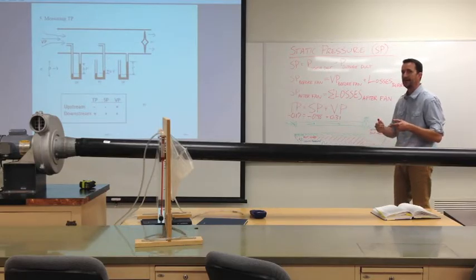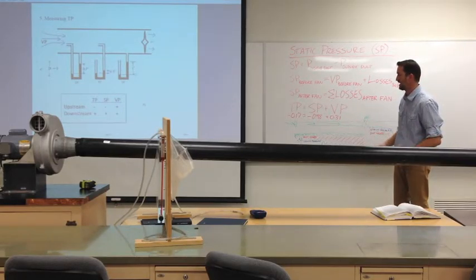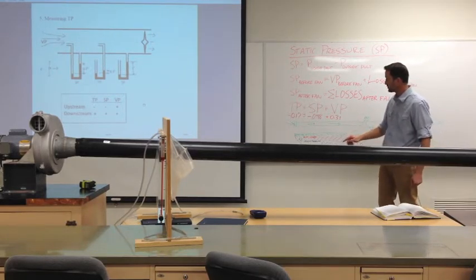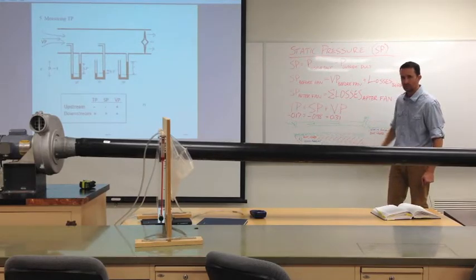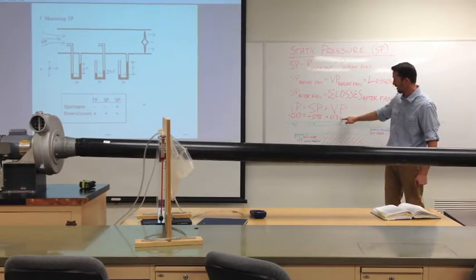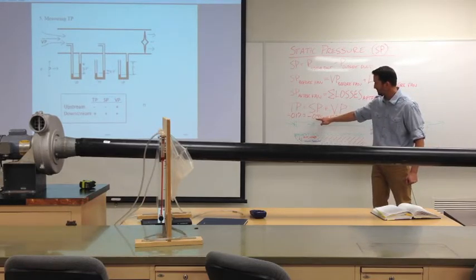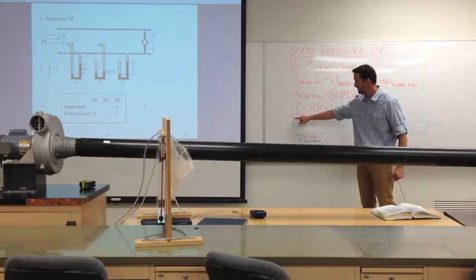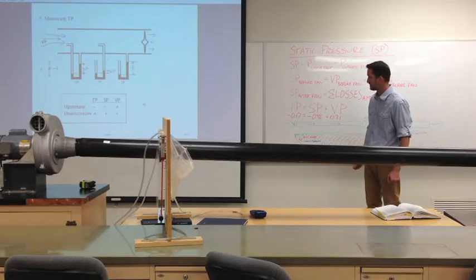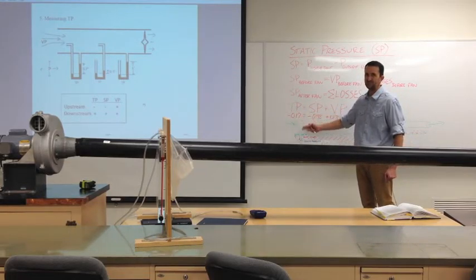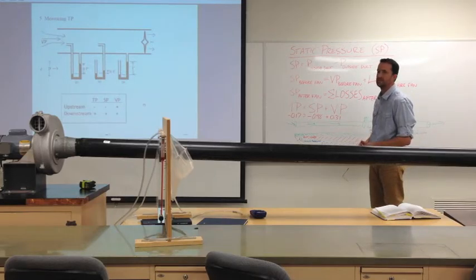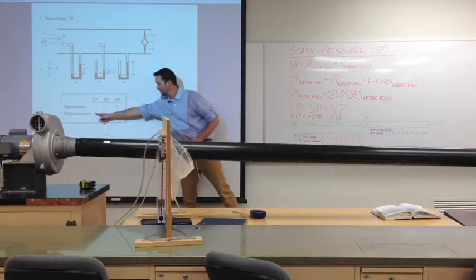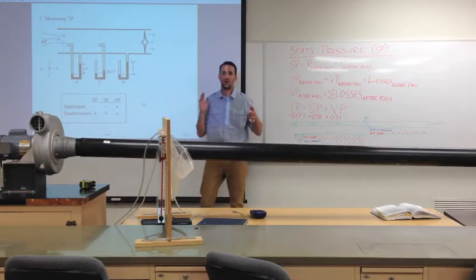Okay, we measure it in head loss as inches of water gauge, or inches that it would push or pull the water up a column. We also measured the velocity pressure, which in our case was positive 0.31. If you add negative 0.48 and a positive 0.31 together, the difference is negative 0.17. So in our ventilation system, we had a total pressure that was negative 0.17, which makes sense because it is suction and it's on the upstream side of the fan. On the downstream side of the fan, total pressure, static pressure, velocity pressure will all be positive.